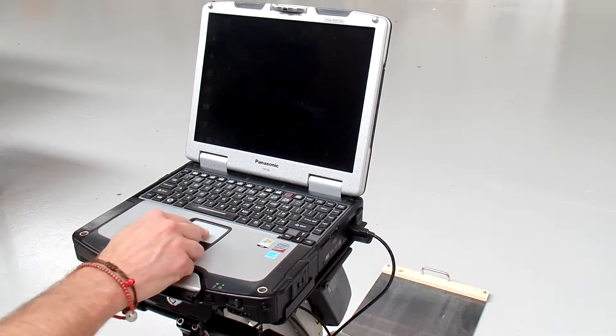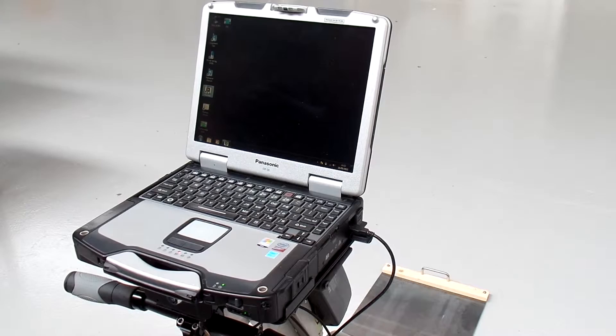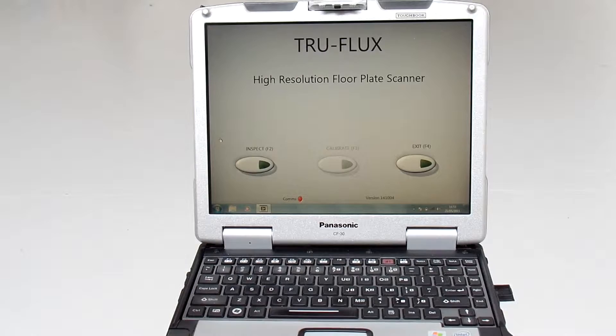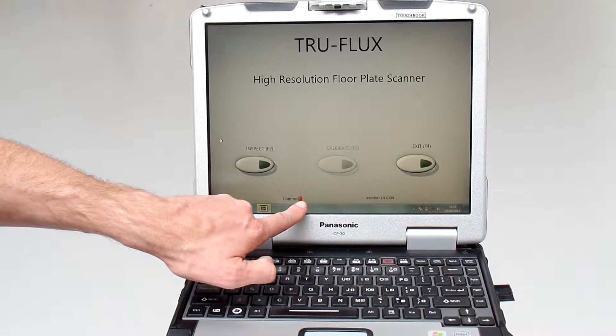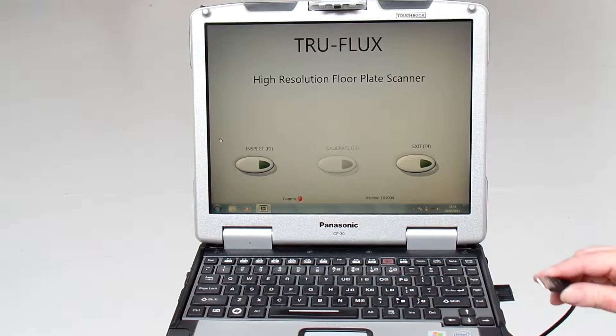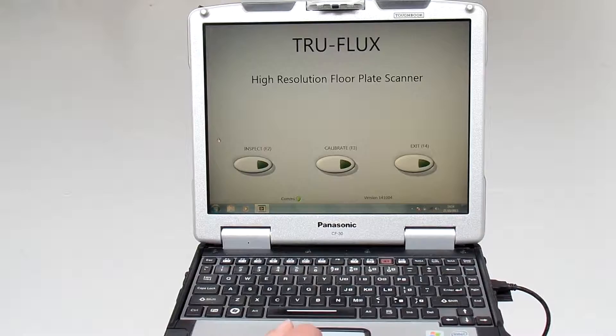Once Windows has been booted, you run the TruFlux software from the start screen by double clicking on the TruFlux icon, and the software will start and communicate with the product. The software has started. There are three buttons on the display to start an inspection, to run a calibration, and to exit the application. There is a communication status light here which will be red until a USB connection is made to the head unit. If we plug the USB cable in, the light will turn green once communications has been established.